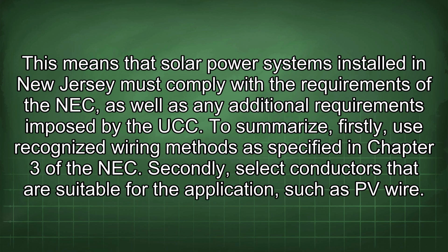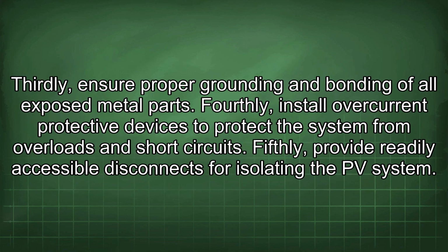To summarize, firstly, use recognized wiring methods as specified in Chapter 3 of the NEC. Secondly, select conductors that are suitable for the application, such as PV wire. Thirdly, ensure proper grounding and bonding of all exposed metal parts. Fourthly, install overcurrent protective devices to protect the system from overloads and short circuits. Fifthly, provide readily accessible disconnects for isolating the PV system.